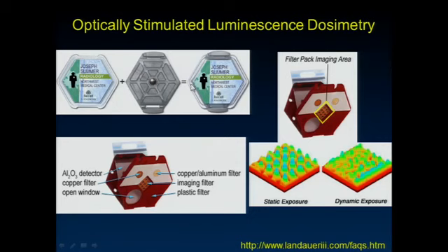The first thing I want you to notice is that this plastic housing has a little circle where the plastic housing is missing. It's only covered with a really thin piece of adhesive plastic put over the surface. And that's the beta window. Because remember, beta has mass, those are electrons. They have mass and they have charge, so they don't penetrate very far through any material. So we actually decrease the thickness of the plastic housing to be able to detect the beta window there.